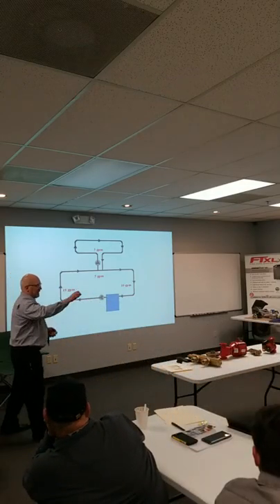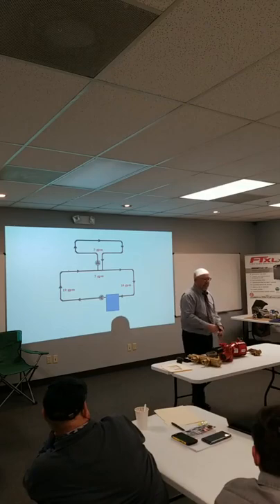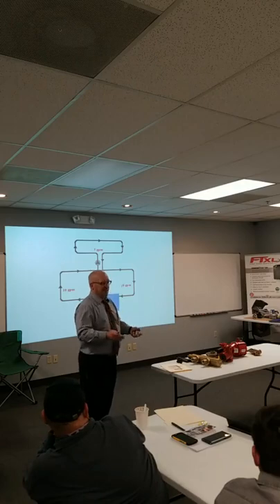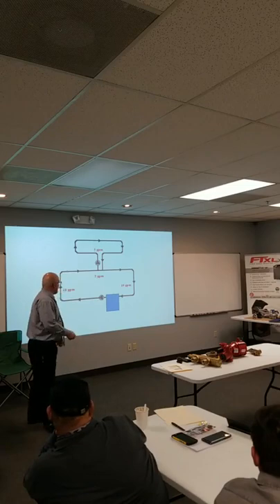Just because that pump has the same face-to-face dimension as this pump, is it the same pump? Absolutely not, and I have this argument all the time. Give me a pump that fits. Well, that doesn't mean you're getting the right pump, just because it fits the same face-to-face dimension. I don't even ask the salespeople. I want to see the pump curves. Give them to me. Look up all the pumps on...